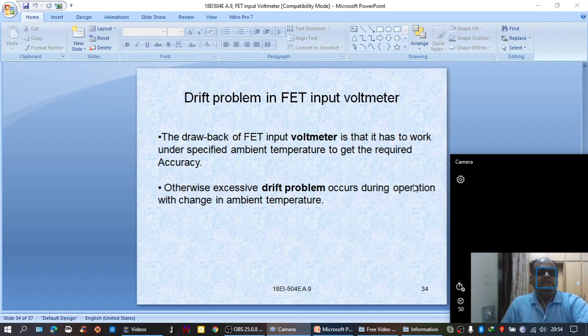Drift means change in the measured value. So here, we have to use the instrument only under specified ambient temperature conditions to get better accuracy. Otherwise, excessive drift problem occurs during operation with change in ambient temperature. When there is a change in ambient temperature, say higher value or lower value, automatically the voltage measurement would also be changing.